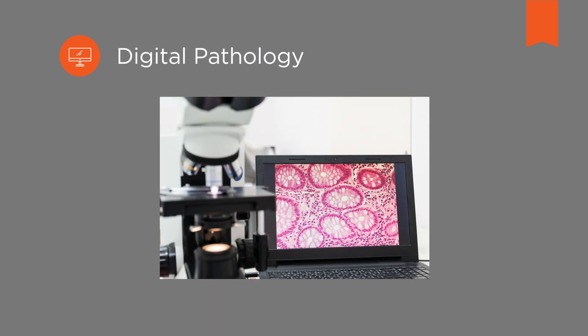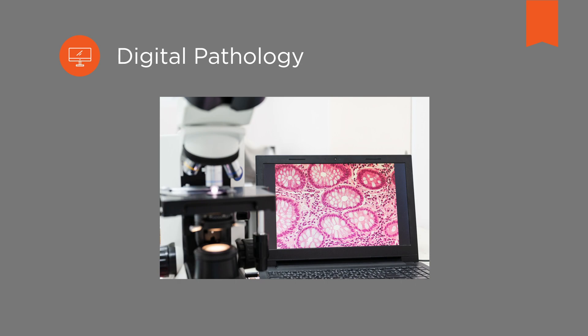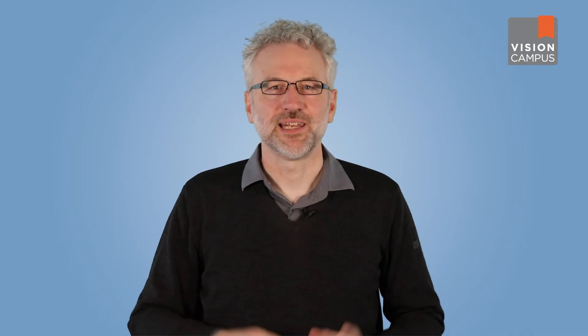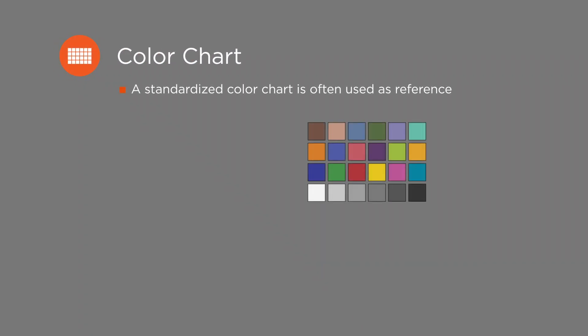For more demanding applications such as digital pathology, where color precision is crucial for analysis, the color settings must be calibrated for the specific setup. Calibration is based on test images under real conditions, which means under the same light conditions as in the intended application. To optimize the color settings, a standardized color chart is often used as a reference.